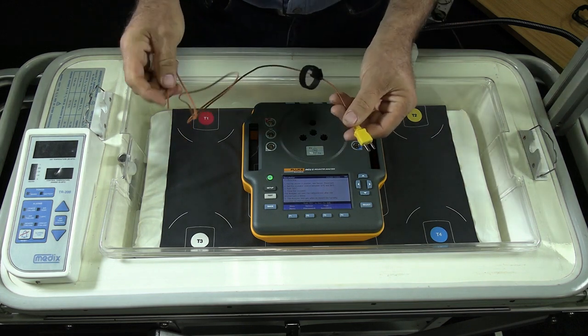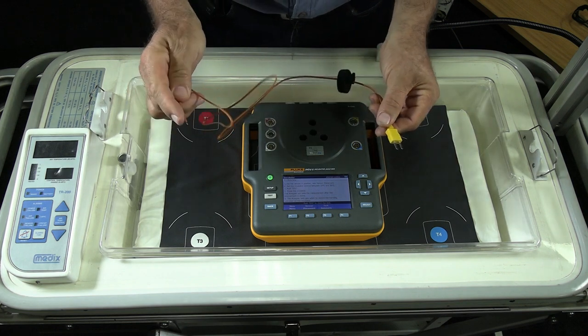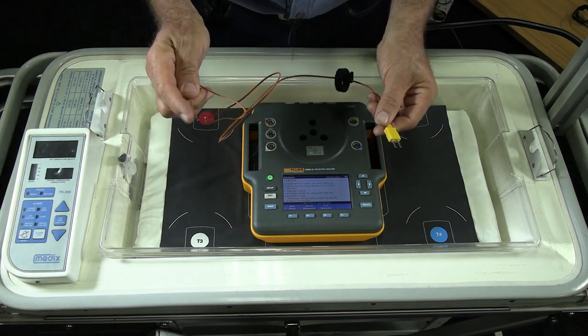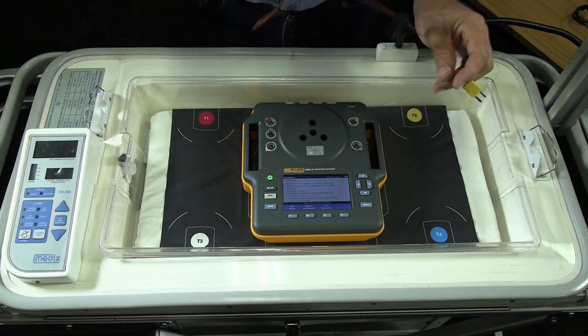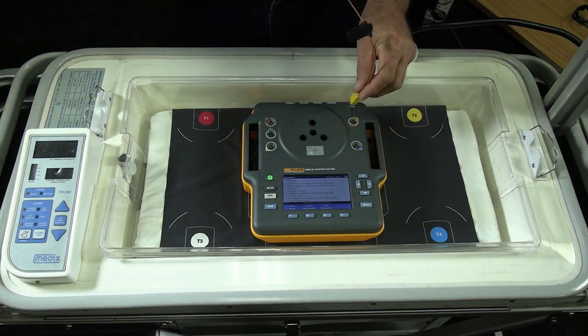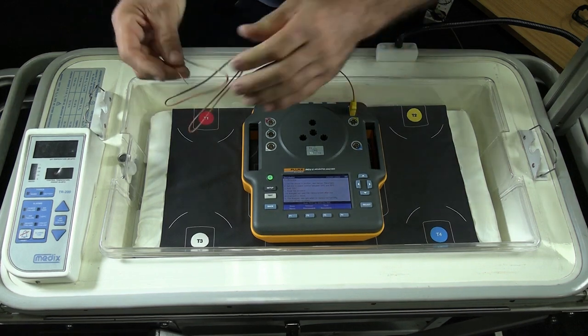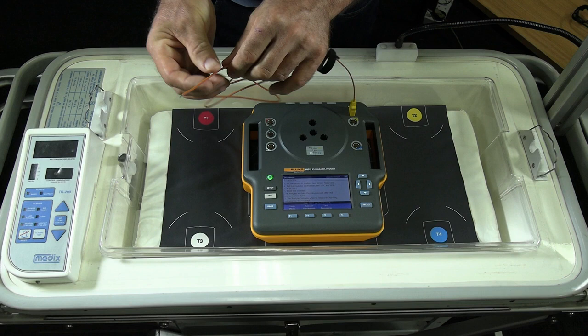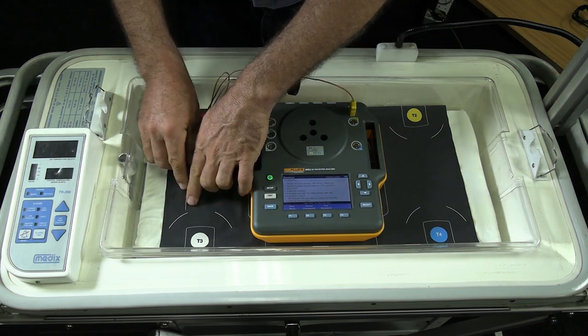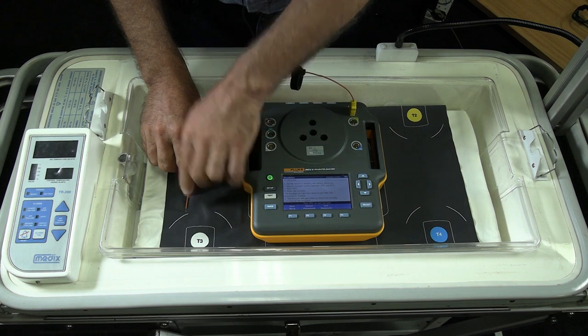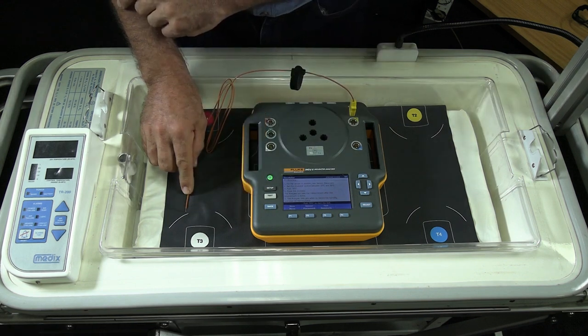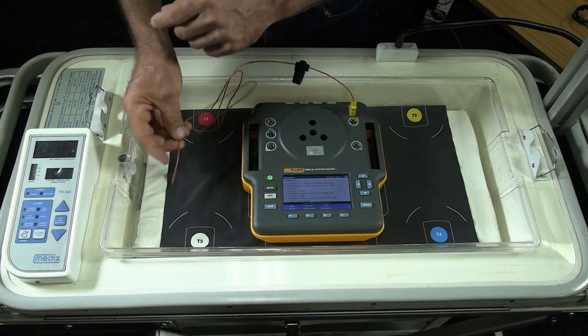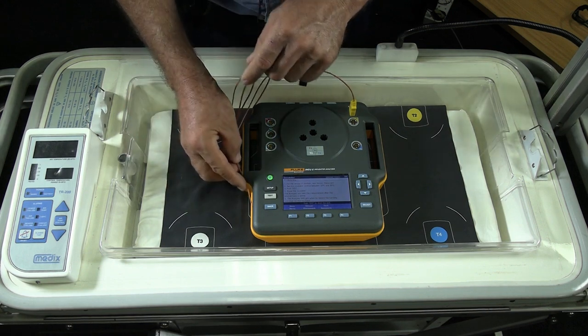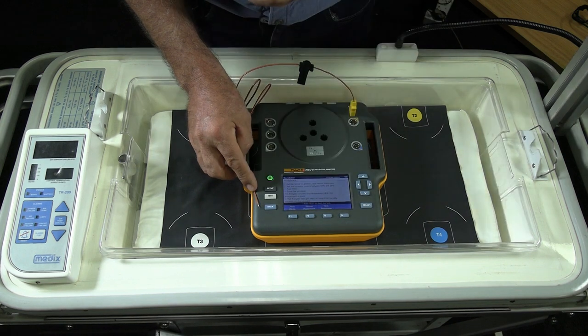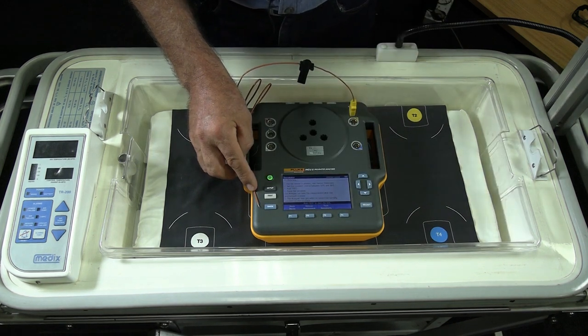Now the K sensor is this. It's got this yellow connector, and in front it looks like just a piece of wire, but it's actually your temperature tip. The K sensor, you see the K type here, just plugs in there, and then you'll use a thermal compound to put on the mattress and maybe use a little plaster across it in order to keep it in place, in order to test the temperature. Or if there's a metal surface or anything around the baby, you can place it on there and put a little plaster over to keep it in position to test the temperature of that particular object.